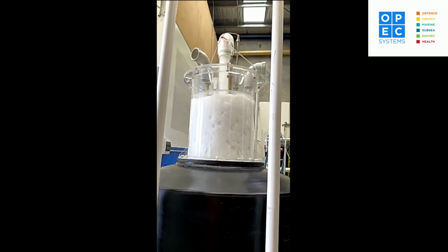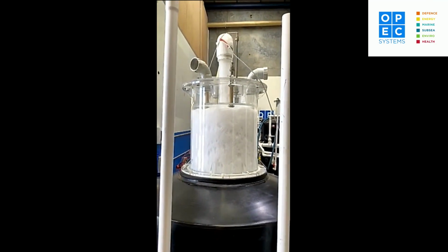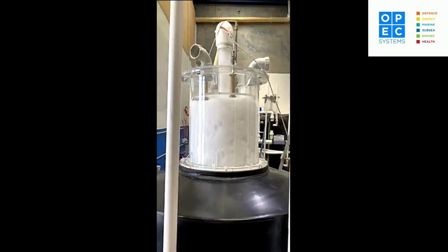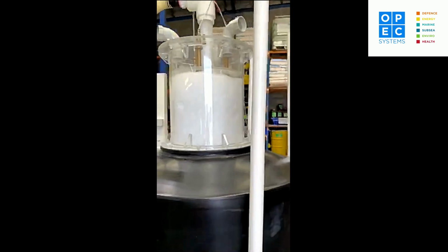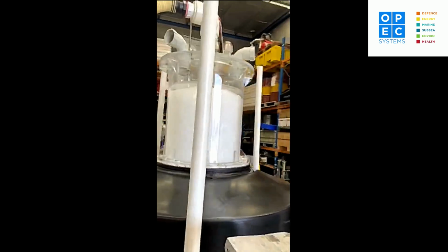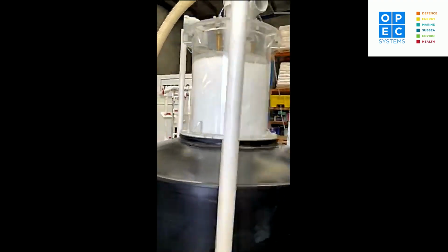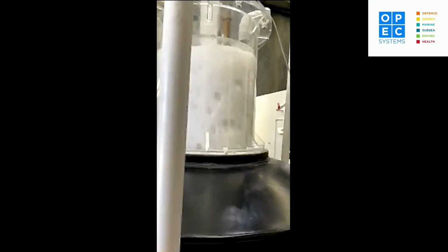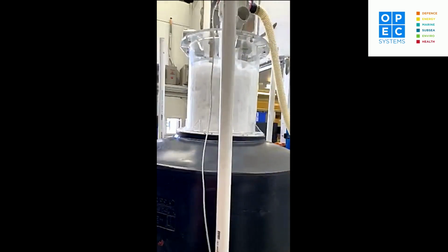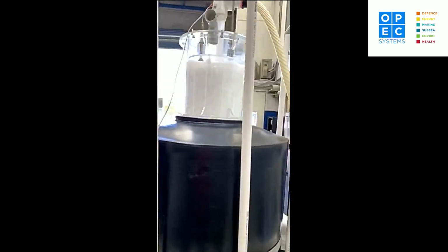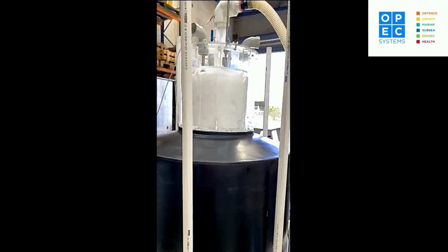So here we've got one of the heads in the mid-sized units that we were working on, and we've got a really healthy foam in that unit. You can see we're starting to crowd it into the top of the head. We move it up to the top where we've got a vacuum extraction system, and if you look carefully you can see that we've hit the sweet spot there. We're drawing off that PFAS enriched foam, which is then transferred to a knockout drum where it quite quickly collapses, ready for the next stage in the treatment process.